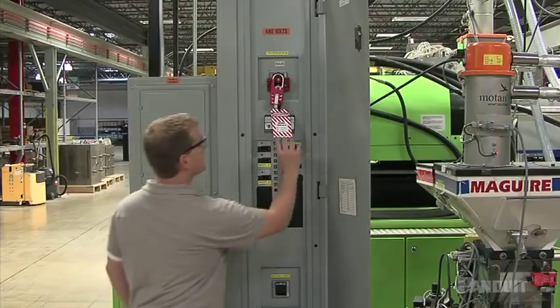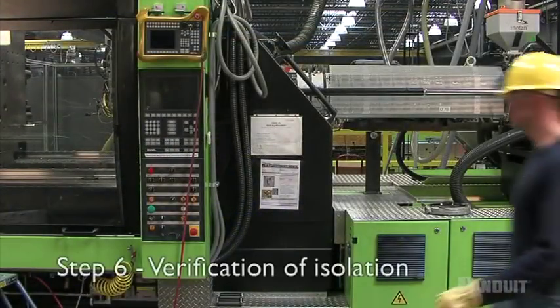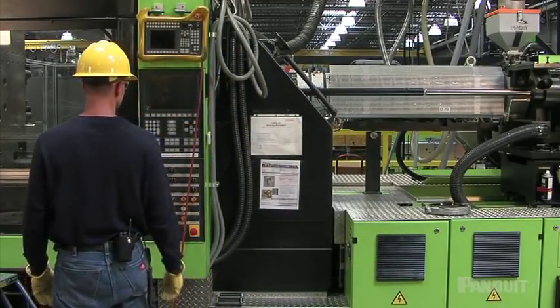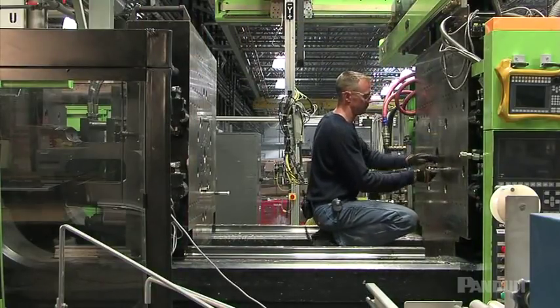These procedures may appear to be excessively cautious, but when a life is on the line, there is no point in taking chances. After affixing the necessary lockout-tagout devices, release stored energy and bring the equipment to a zero mechanical state. Even though you have locked the levers, valves, or switches in place, check them again and verify that all sources of energy are isolated by testing if necessary. Make sure no one is able to put them back in the on position. Retest all on-off controls and leave them in the off or neutral position. When the machinery is completely de-energized and all movement has stopped, it's safe to go to work.